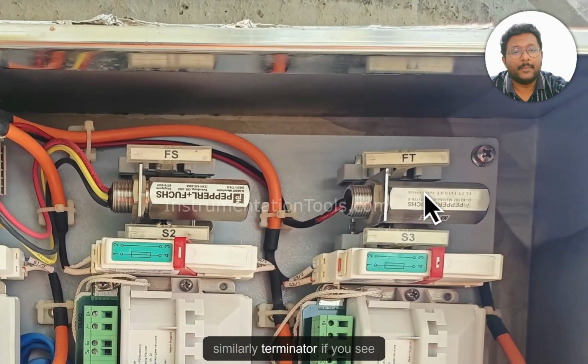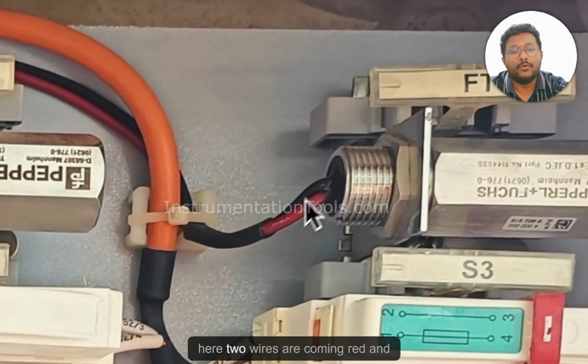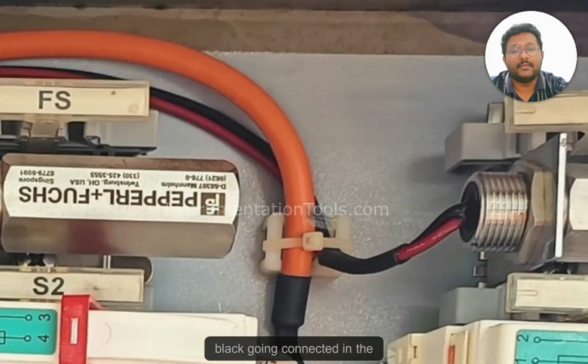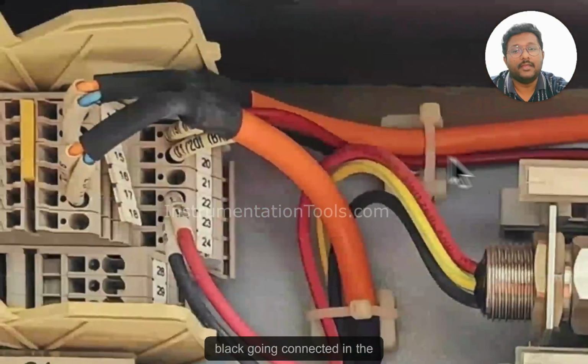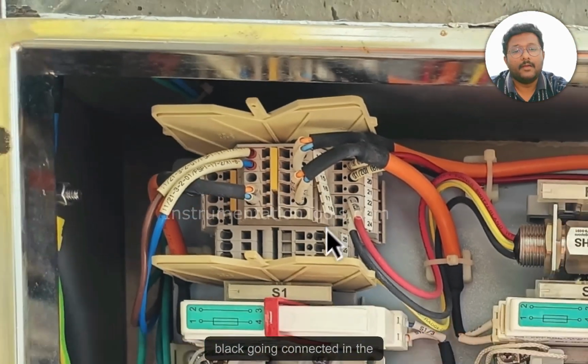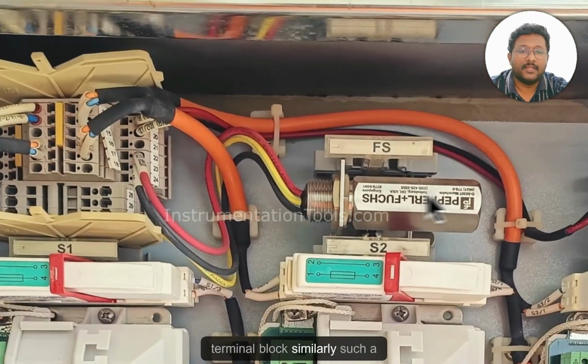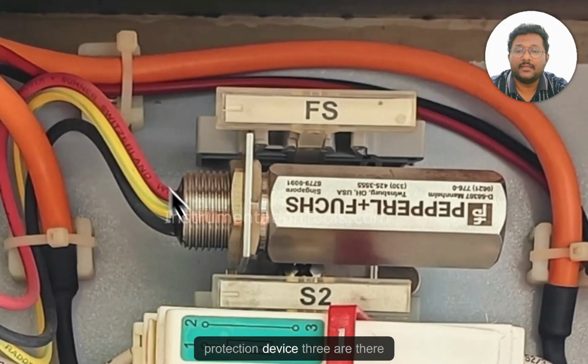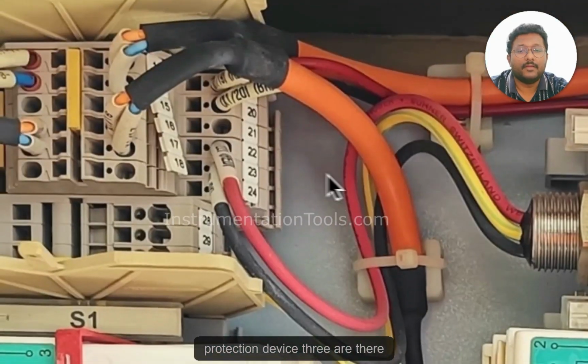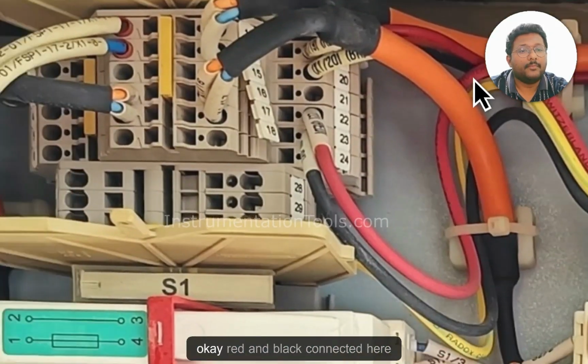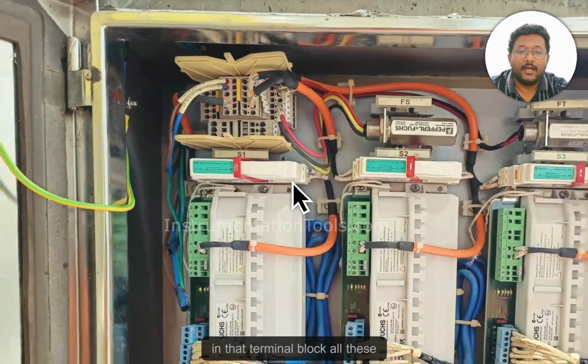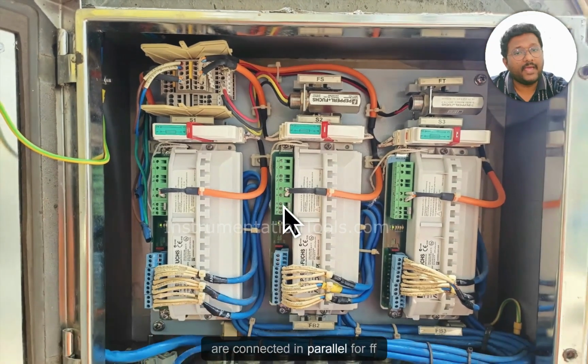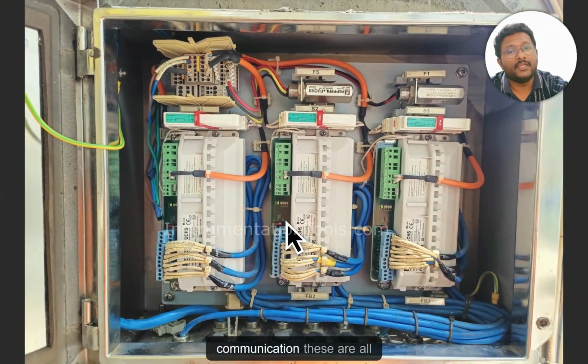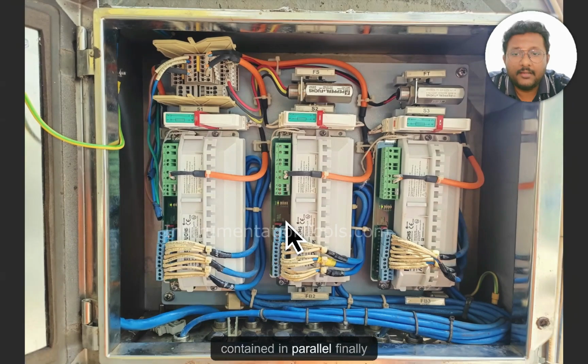Similarly, the terminator, if you see here, two wires are coming, red and black, connected in the terminal block. Similarly, the surge protection device, three are there. Red and black connected here in the terminal block. All these are connected in parallel. For FF communication, these are all connected in parallel.